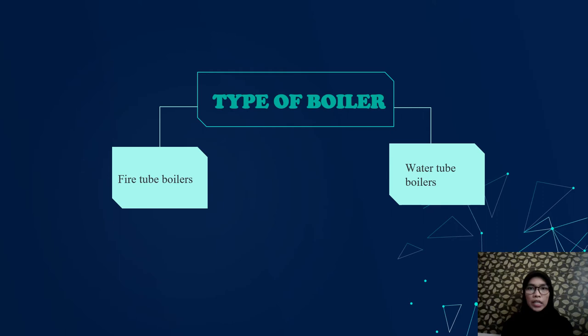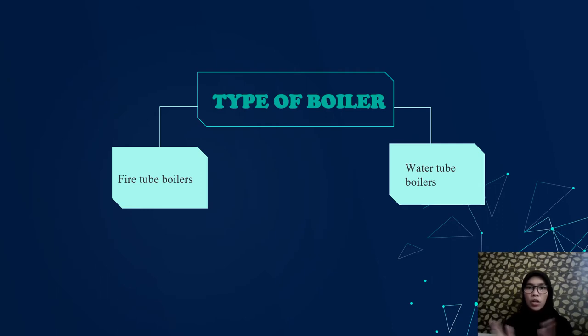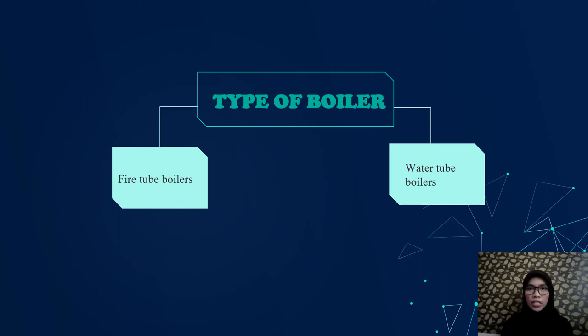There are two primary types of boiler: fire tube boiler and water tube boiler. In a fire tube boiler, hot gases of combustion flow through a series of tubes surrounded by water. For a water tube boiler, water flows inside the tubes and the hot gases from combustion flow around the outside of the tubes.